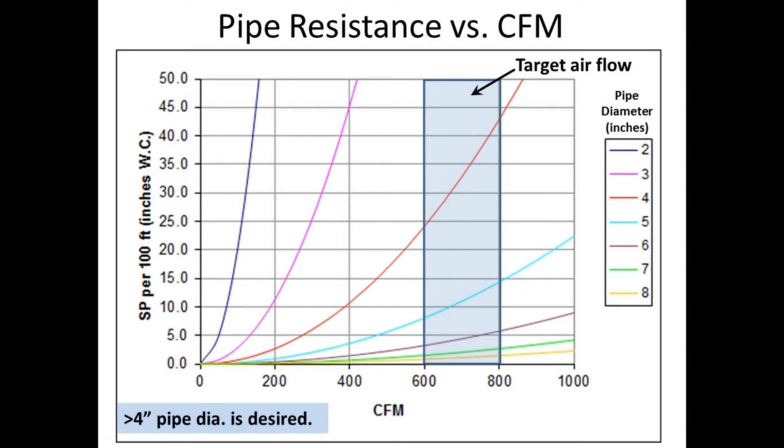If we go up to even three inches, okay, now we've gotten above 200 CFM, but still look at the static pressure. Even at 200 it's up around 10. Again, not really what we're looking for. We're looking for a target range, at least for my shop, anywhere between 600 and 800.